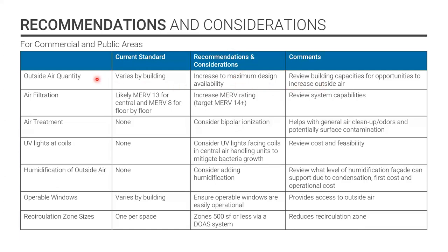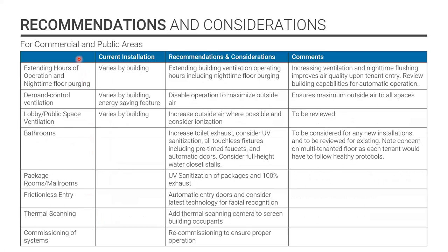Outside air quantity, about increasing the air quantities in buildings. Air filtration, it could be MERV 13 or 8. Let's go to a 14 if we can, and certainly 13 is what ASHRAE recommends. Air treatment systems, we're saying you can consider some of these technologies: UV lights, humidification, operable windows, if you have them, they're great. Recirculation zone size, extending hours of operation, disabling demand control ventilation, lobbies and public spaces where people are, increase the outside air ventilation.